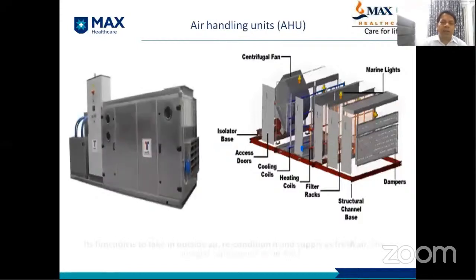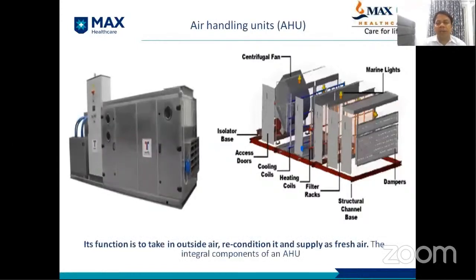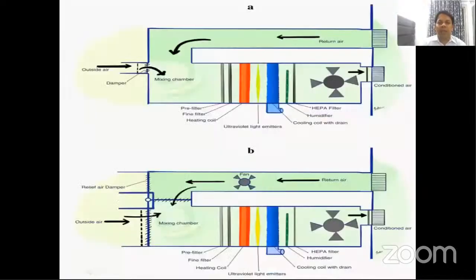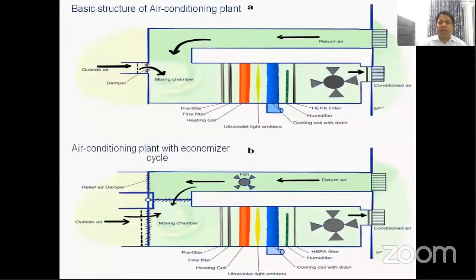The AHU's function is to take in outside air, recondition it, and supply it as fresh air. If you see the detailed diagram of how these HVAC systems and the AHU work, here you can see the outside air, then the damper, then the mixing chamber, then the pre-filter, fine filter, heating coil, ultraviolet light emitters, then the cooling coil and drain, then the humidifier. Last is the HEPA filter. Before the HEPA filter, a lot of stages occur so that the HEPA filter has maximum effective capacity. Then the conditioned air, then the return air, then it goes again.